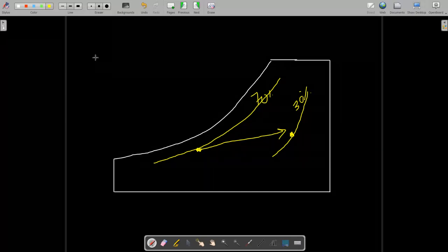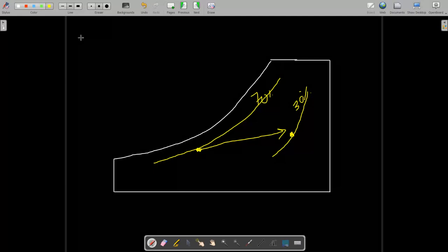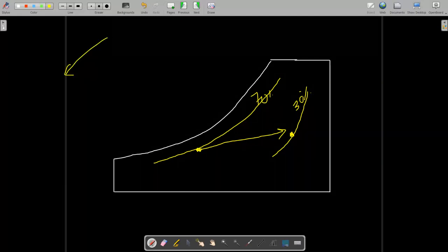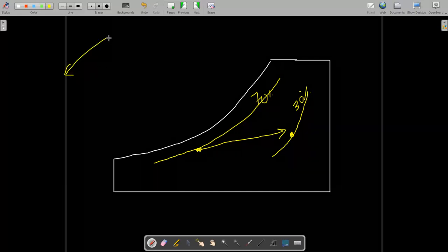You can see here that the process slope is upward. But you have seen that for dehumidifying, the slope is generally downward, in all cooling and dehumidification and heating and dehumidification. But why here is it upward? Because the temperature change is sensibly more, but the absolute humidity change after the final condition is very less. Only the relative humidity changes, but absolute humidity is increasing. Why is this increasing? Because in the question one statement is given.